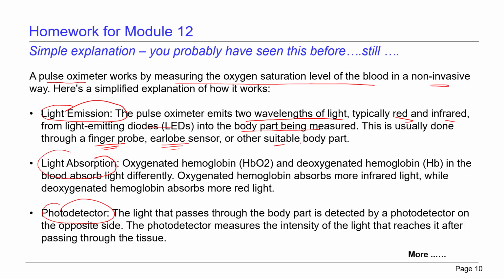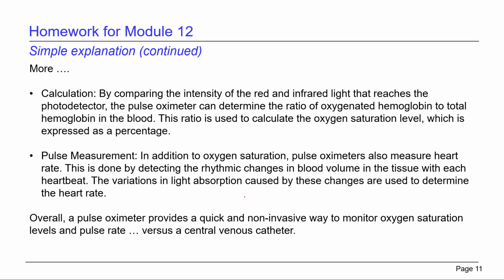When we talk about other suitable body parts, this is anything where we can pass the light through. And interestingly, in pediatrics, it happens to be the foot. Kind of a surprising point there. But essentially, oxygenated hemoglobin and deoxygenated hemoglobin absorb light differently, and we take advantage of that in this measurement system. While the oxygenated hemoglobin absorbs more infrared light, the deoxygenated hemoglobin absorbs more red light.